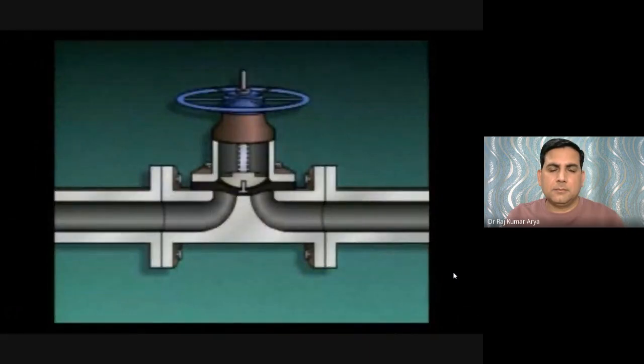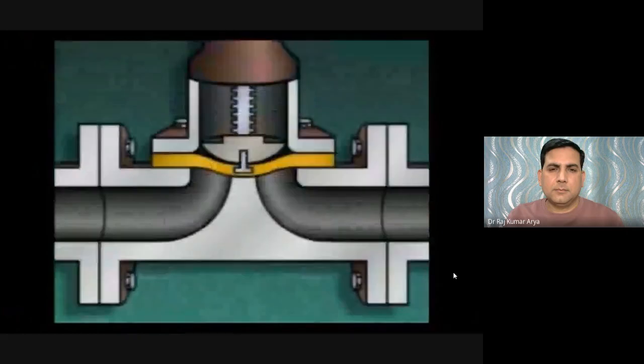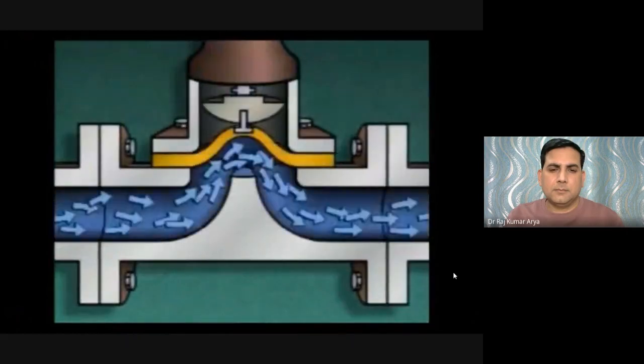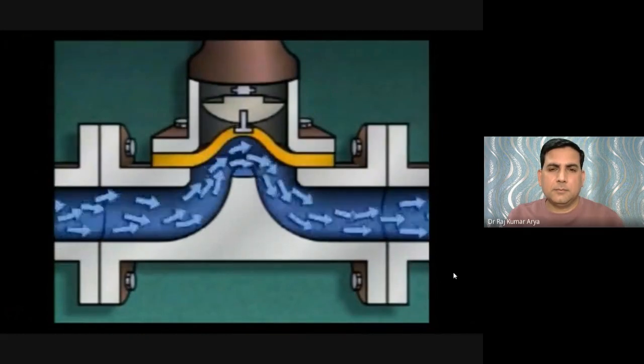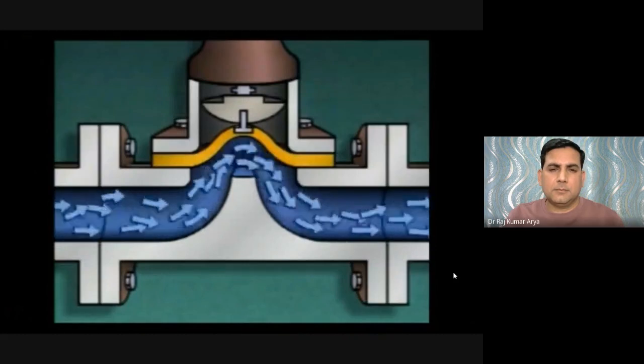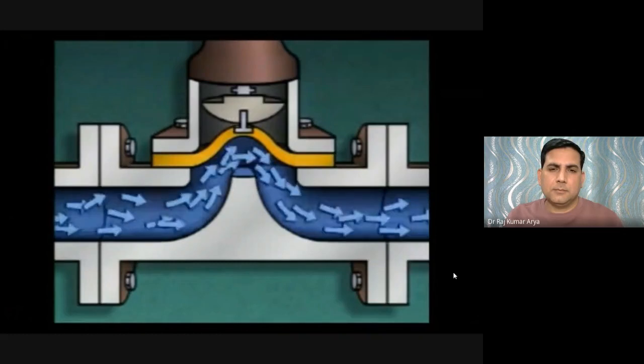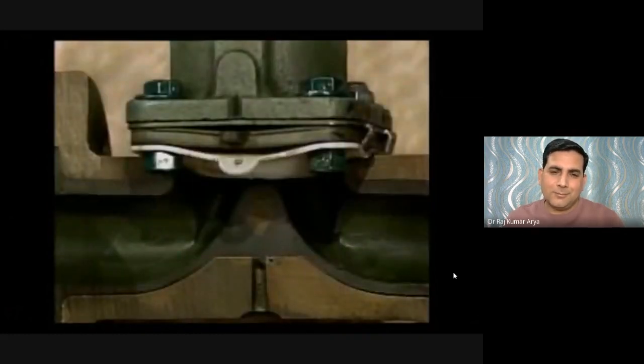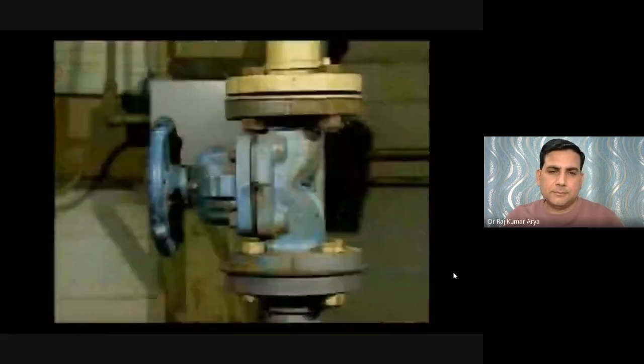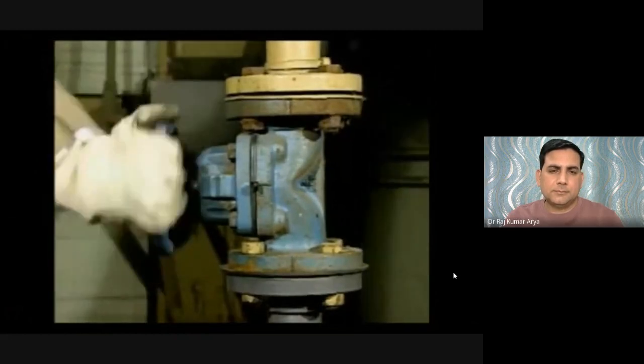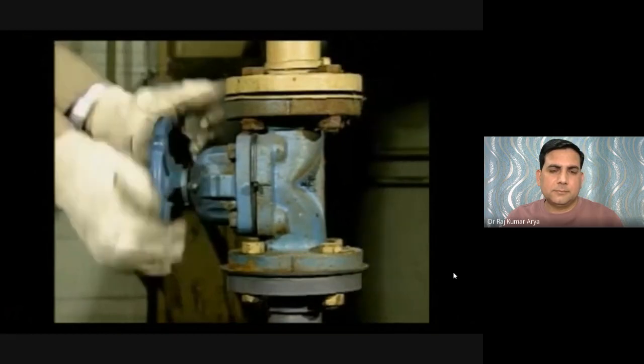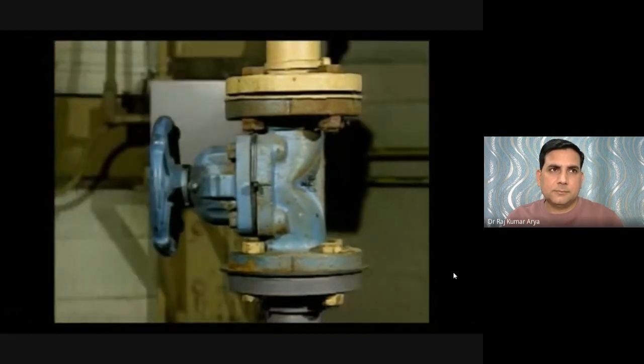The diaphragm also serves as a seal that keeps fluid from contacting the operating parts of the valve. This makes diaphragm valves well suited for systems carrying corrosive materials such as acids and caustics. Some diaphragm valves contain a plastic liner to protect the valve body. When operating a diaphragm valve, be careful not to use excessive force when closing it, as this can cause the plunger to jam the diaphragm against the seating area and cut the diaphragm, causing leakage.